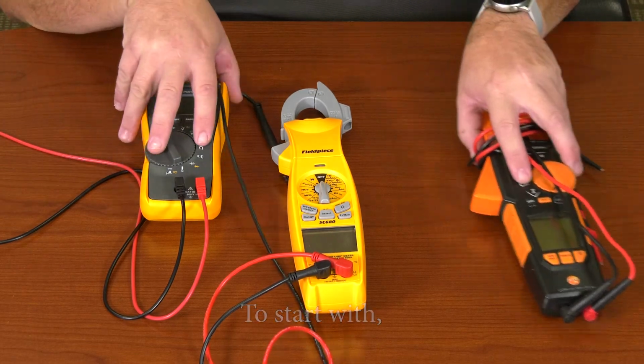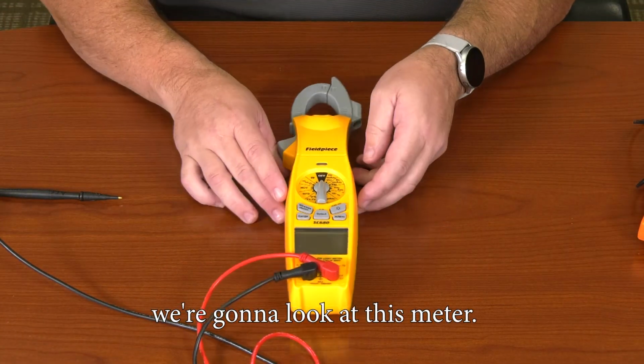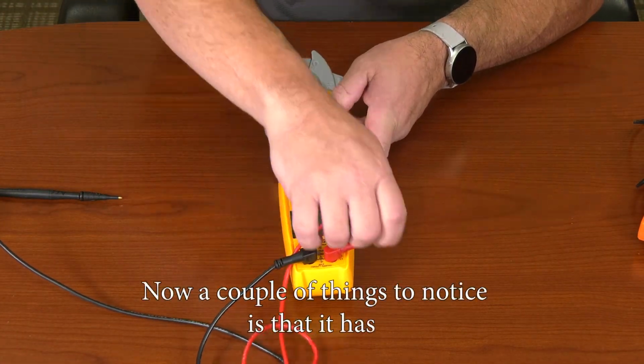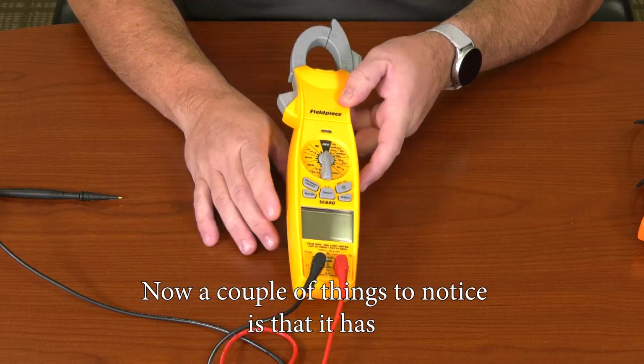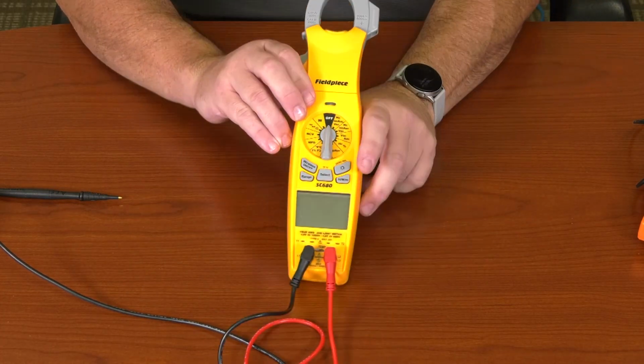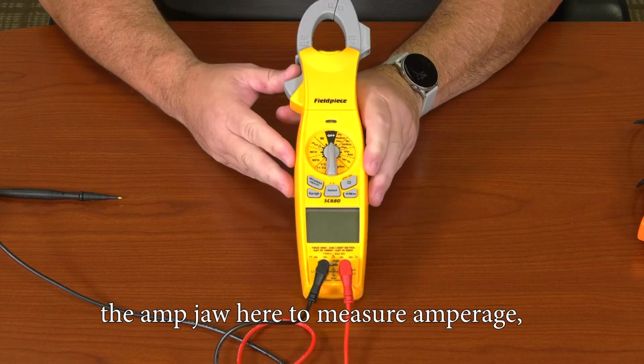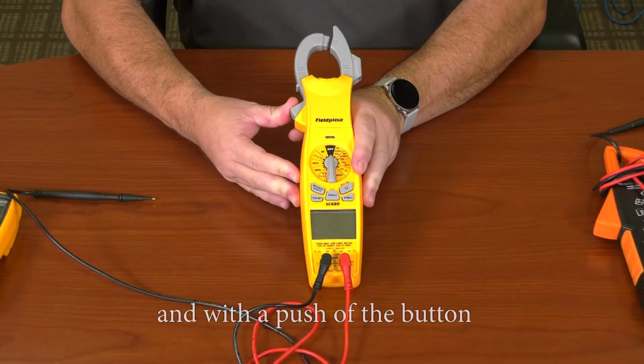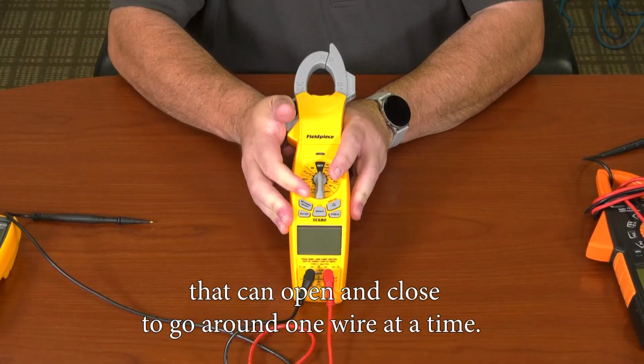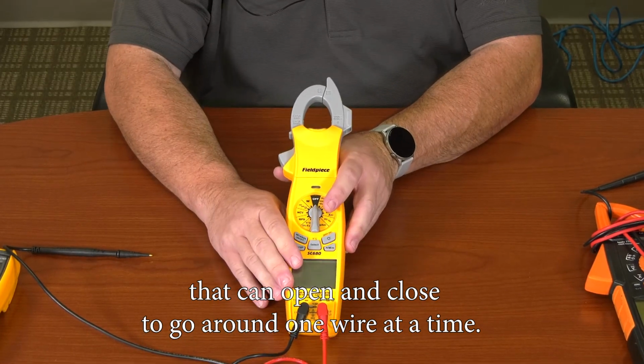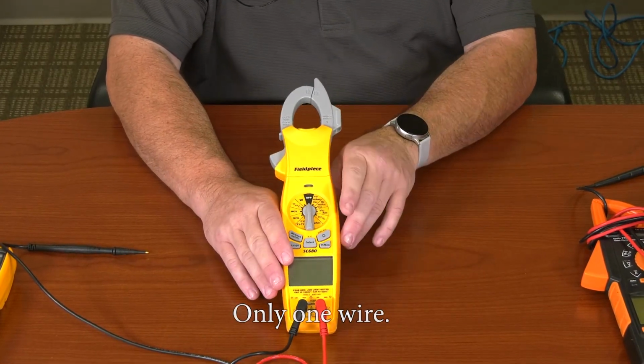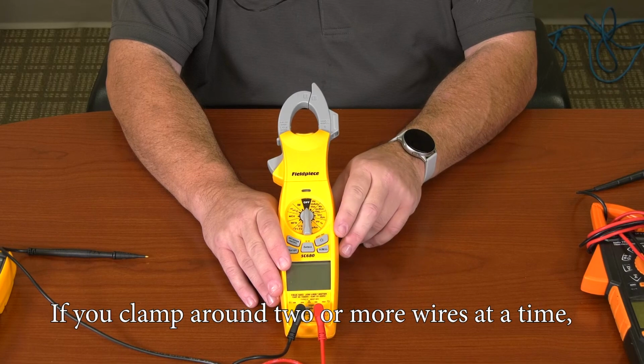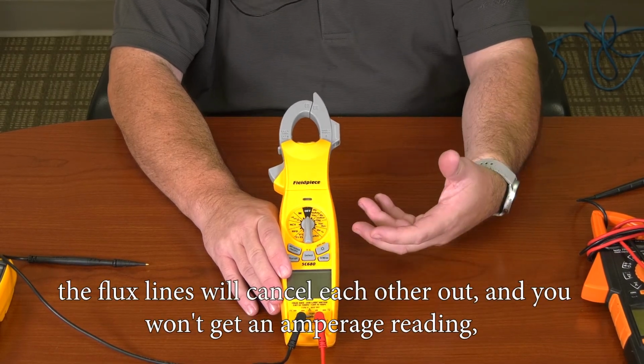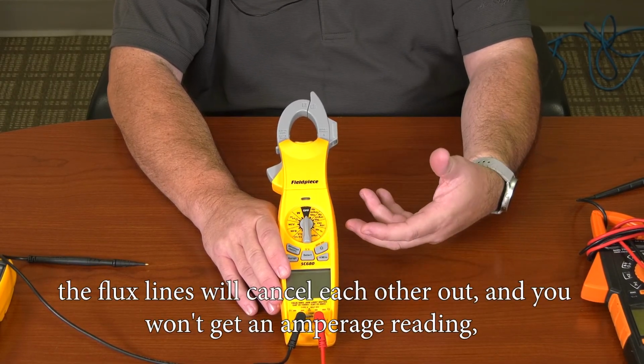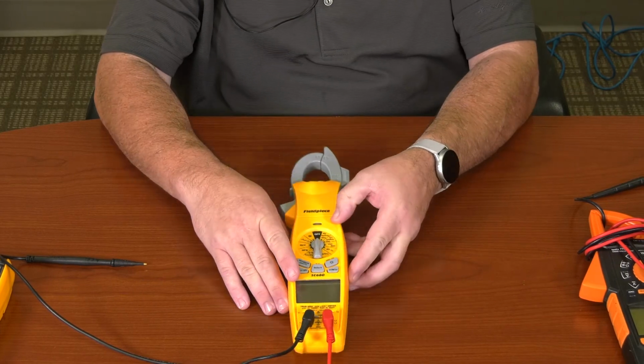To start with, we're going to look at this meter. Now, a couple things to notice is that it has the amp jaw here, can measure amperage, and with a push of the button, that can open and close to go around 1 wire at a time. Only 1 wire. If you clamp around 2 or more wires at a time, the flux lines will cancel each other out and you won't get an amperage reading, which could be unsafe.